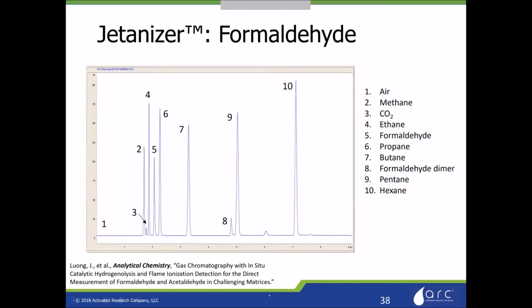And the last exciting application I want to talk about is that of formaldehyde in the Jetanizer. This one was actually born out of surprise, and Jim Luong had looked at it. We weren't sure the Jetanizer would be capable of this, and it is very difficult to do formaldehyde analysis on any instrument. Most of it's done on LC with difficult derivatizations and difficult calibration. It has been attempted on GC. There are companies that produce standards that do not work, and permeation tubes, for example. A number were tried from different vendors, and they were off by factors of 10 or more in terms of the stated concentration. So it's a very difficult molecule because of its reactivity, and in the case of permeation tubes, questionable models of its diffusion through the tubes.